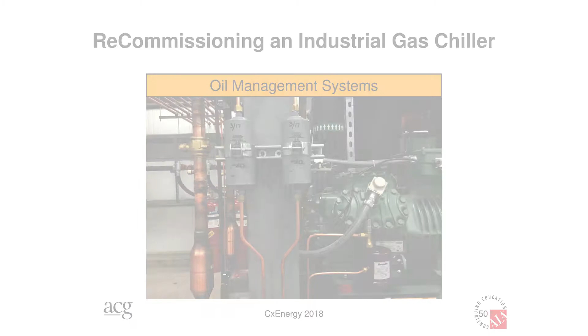What we added were coalescing oil filters for each compressor, each tandem. So there's 4 of these. This coalescing oil filter, the refrigerant, the hot gas comes in the bottom. The oil gets separated out of it, and the gas continues up and out into the system while the oil goes through this tubing up into an oil reservoir. Oil reservoir is at high pressure, and then it goes through a pressure regulator and over to this float valve on the compressor crankcase.